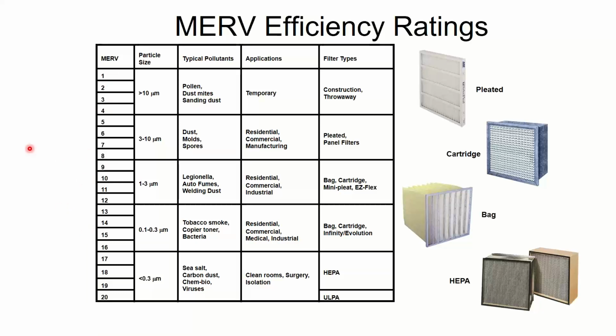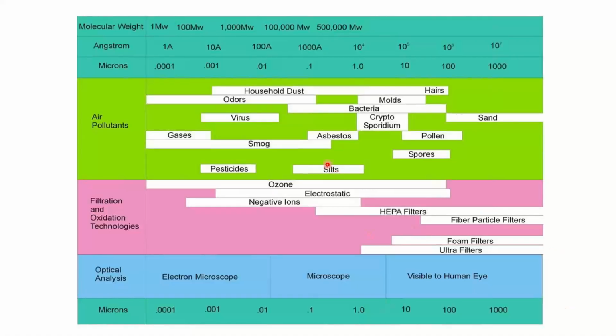Most of the filters in your existing systems are probably like MERV 8. That's pretty common. MERV 6 is the minimum required by ASHRAE 62.1, so you shouldn't have anything worse than that. But MERV 8 is a pretty common one. Residentially, MERV 8 to MERV 10 is fairly common. But none of those are going to do anything for COVID or any of these small things. It's not going to do anything for odors. It'll only get like half of your dust. Some of the dust over here, yeah. Some of the dust over here, no. Right? So it's not really that helpful. We'll go through a few more examples of that.